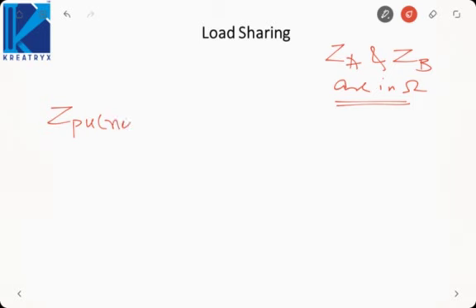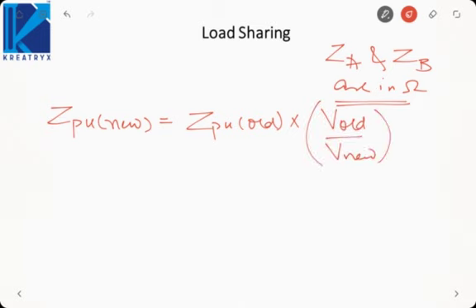If we want to change the base, Z per unit new is equal to Z per unit old into V old by V new square into S new by S old. Base values are only two: the voltage and the power. The voltage rating and the kVA rating, these two are my base values. So if you want to change the base of any value, you must apply this expression.